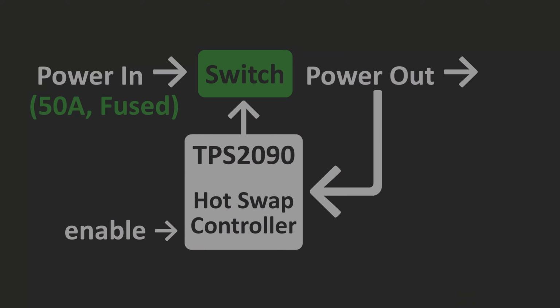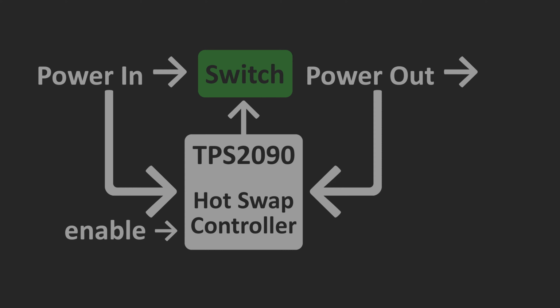There are hardware fuses that are correctly rated on the board to provide this basic level of not melting things protection, but something software resettable has obvious benefits. Another feature of the hot swap controller is the UVLO, or undervoltage lockout. While providing another mechanism to introduce nuisance trips, this prevents over-discharge of our connected batteries.